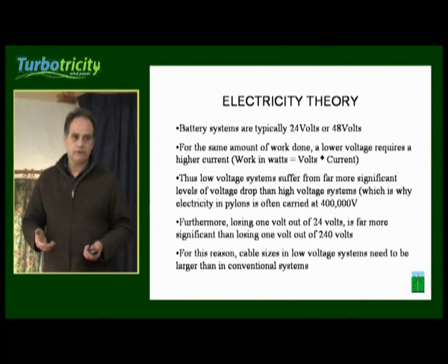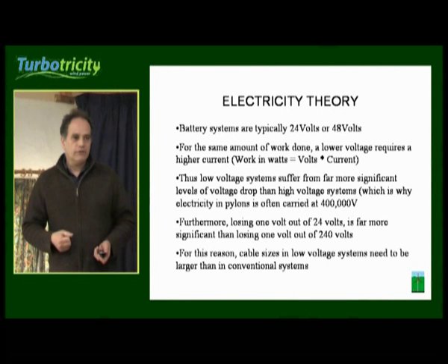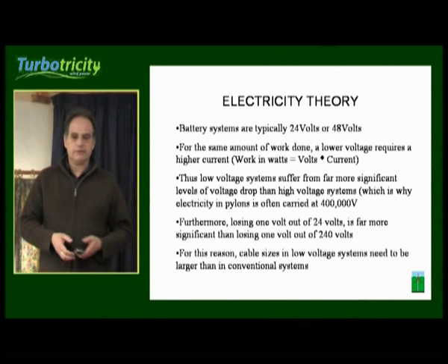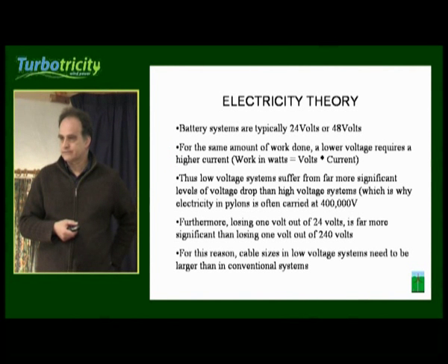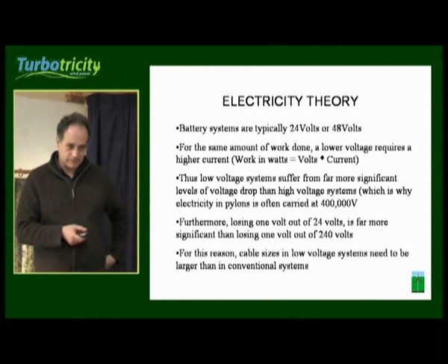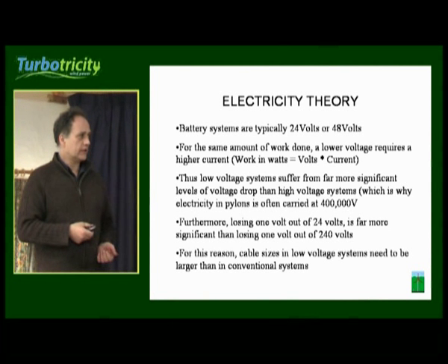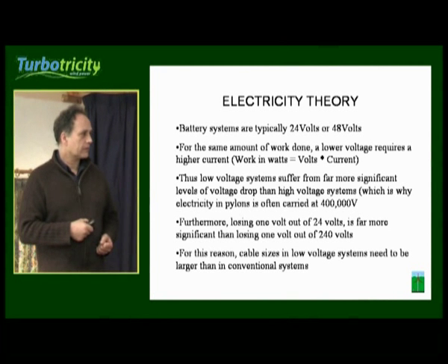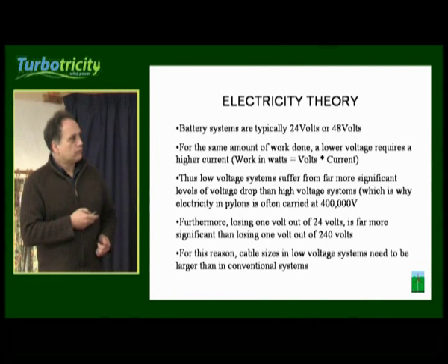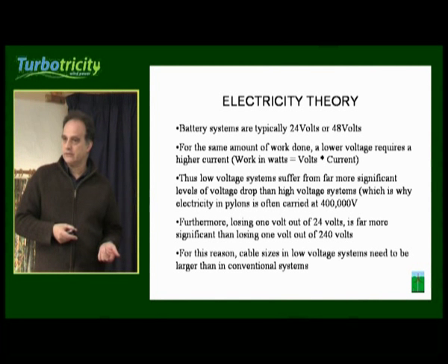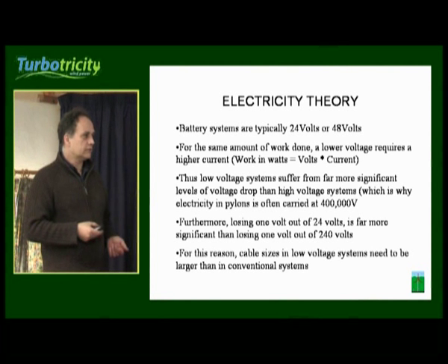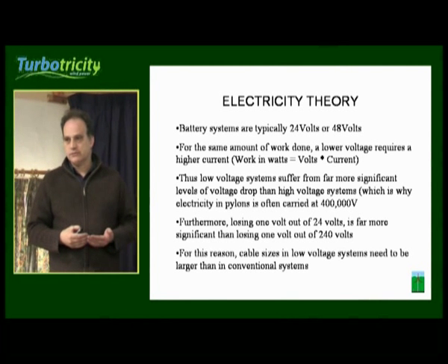Now, if we put in a wind turbine and we have a battery system and we have a choice between, say, 24 volts and 48 volts — for the amount of work done, you're looking at the voltage multiplied by the current. So a low voltage system would require twice the current of the higher voltage system. That's one of the reasons why we carry electricity along pylons, sometimes at 400,000 volts — in the States at even higher levels than that. If you lost, say, one volt out of 48 volts, you'd be losing roughly 2% of your power. So the greater the voltage drop and the lower the voltage, the greater the loss is.